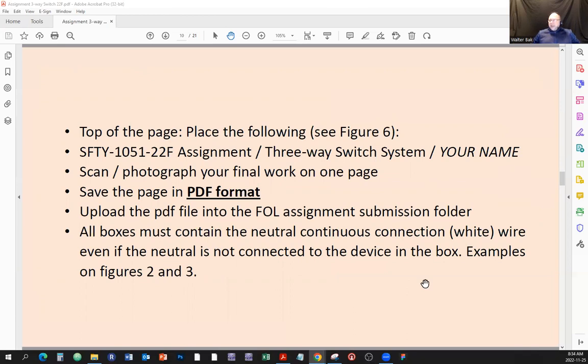This is the second, third, or fifth time I'm mentioning the neutral rule because it's important. Sometimes you might think it doesn't make sense, but consider that ten years from now you might want to mount a dimmer or other device that requires a neutral connection back to the electrical panel. If you don't have it there, you won't be able to mount it. So even though it's not being used, the neutral has to be provided.